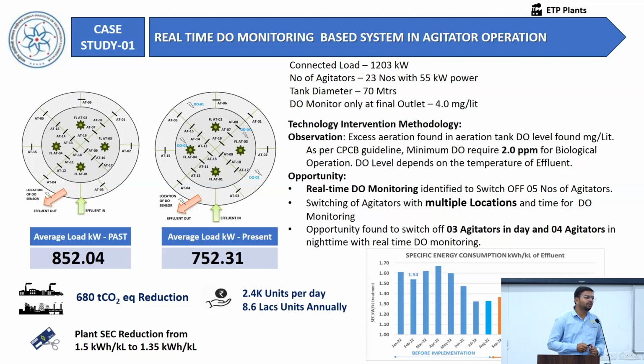Depending upon the DO level, they can switch off or switch on the aeration blowers as per need. With implementation of this ECM, the earlier power consumption for this aeration activity was 852 kilowatt at the instant, when all aeration blowers are consuming. There are 23 blowers in the system.